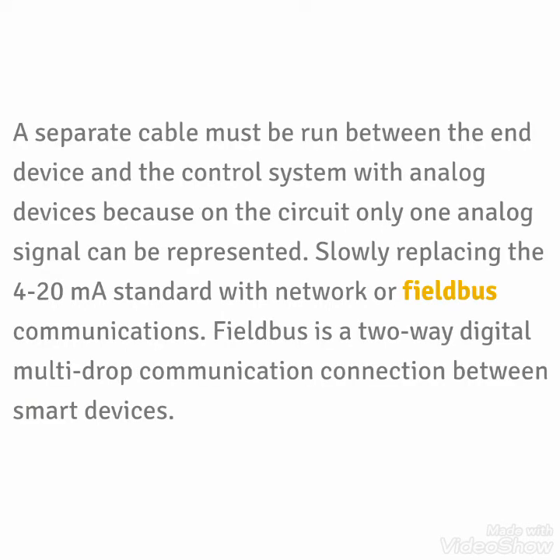A separate cable must be run between the end device and the control system with analog devices because on the circuit only one analog signal can be represented. Fieldbus is slowly replacing the 4 to 20mA standard — it is a two-way digital multi-drop communication connection between smart devices. So for analog we need a separate cable for each instrument, but with fieldbus communication we can use a single cable for signals from different instruments.